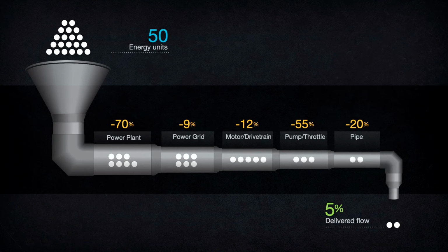Also, as you go back upstream, the components get smaller and cheaper, reducing the total capex. So always start your savings downstream — start at the end, start with intent, with purpose — and then your design logic flows back upstream in the opposite direction to the energy flow.